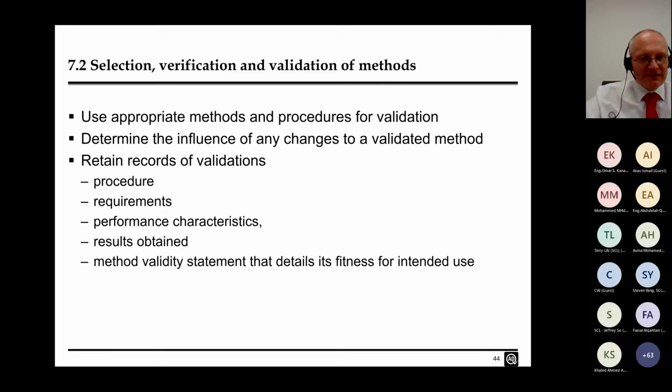If you're doing validation, you need to use appropriate methods and procedures. There is a lot of information in the standard, and there's lots of information elsewhere to help you with this. You need to determine the influence of any changes to a validated method, and you need to retain records of the validation, the procedure, the requirements you were validating against, performance characteristics, the results obtained, and importantly, a method validity statement.